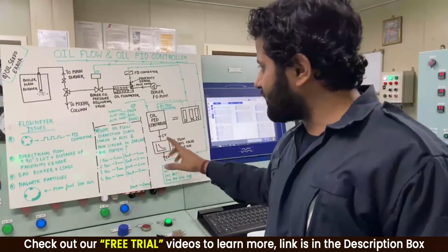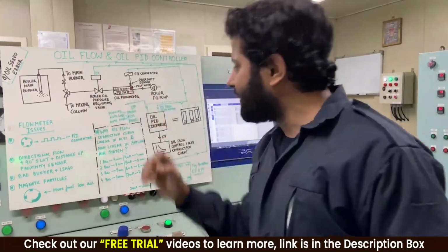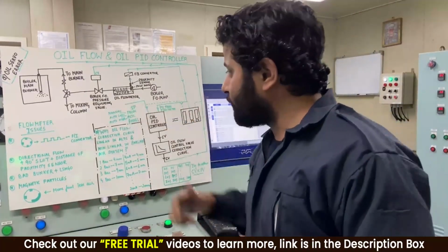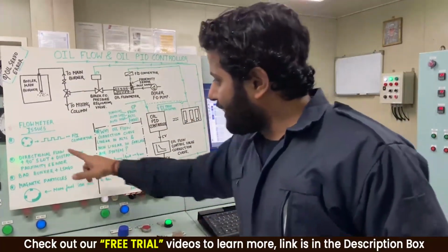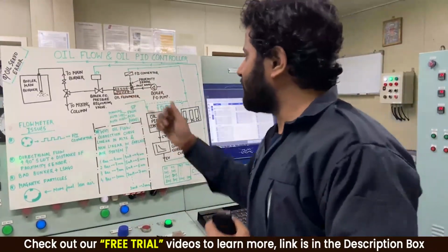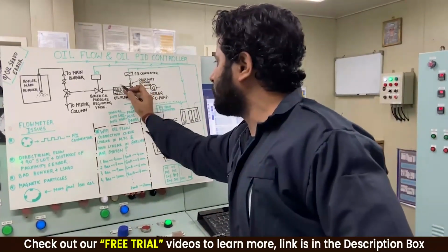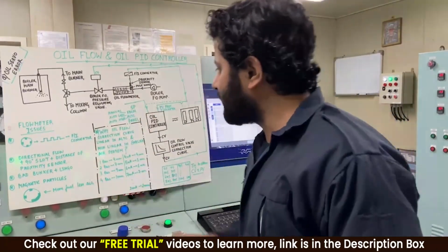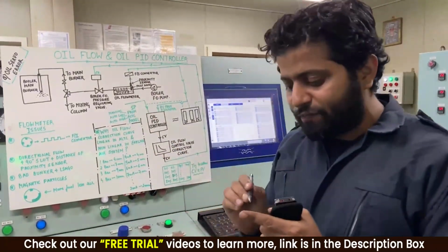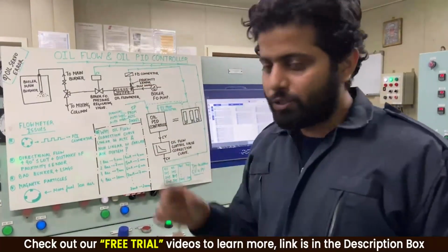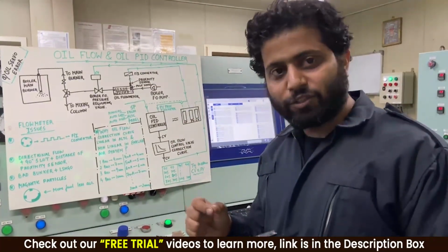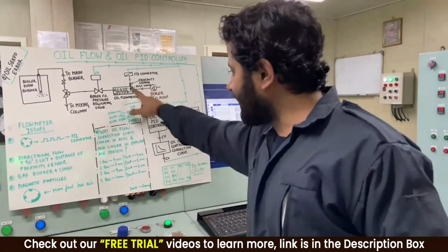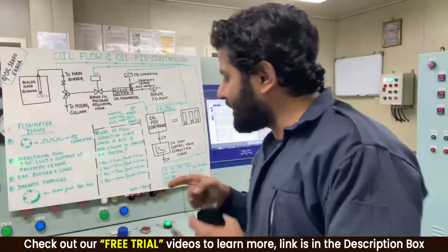Now I have to discuss this, but before that let me talk about this flow meter a bit in detail. When you take this flow meter, there is a particular direction given. You always have to fix this flow meter in that particular direction. That is very important. Another thing you have to remember is that this proximity sensor should be at a fixed distance from the pole wheel. You should not change the distance, because once you change the distance, it becomes erratic and things change, right? Third thing is that there is a 90-degree slot.